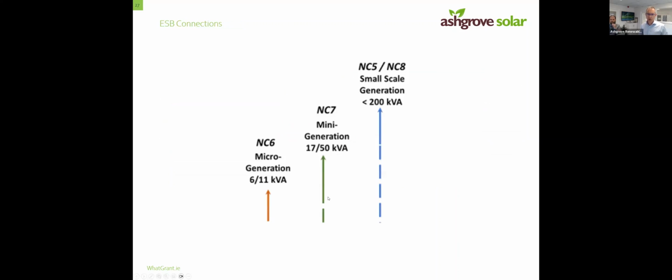Okay, so then, John, do you want to talk about that bit? Just going back, the grants are actually linked to the size of the panel system that you put on. So you don't have to put on a 300 kilowatt inverter for 300 kilowatt panels. It's recommended that you put on a smaller inverter. Those inverters can typically take 150% of the load. So for a 300 kilowatt system, you might put on a 200 kilowatt inverter.